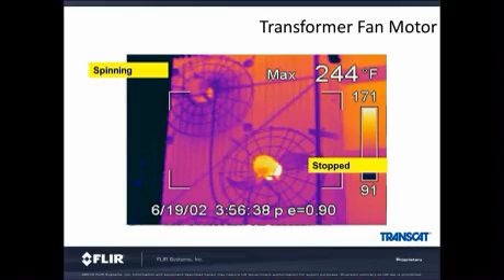By not cooling a transformer, it can have drastic results for the substation. When transformers fail, they cause major damage to all around them, especially if they explode. The premature loss of a transformer is a major problem for the utility. We will be discussing that later in a white paper given by one of our customers. As you know, transformers are not sitting on the shelf. It can take up to a year to get a replacement.